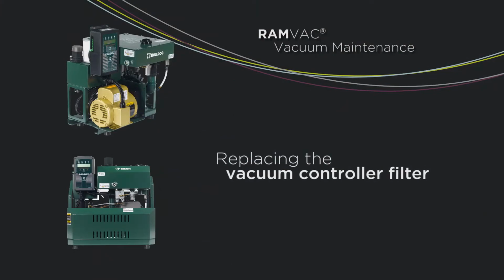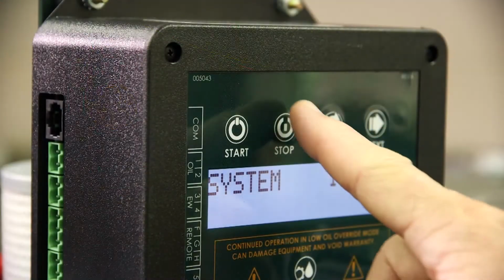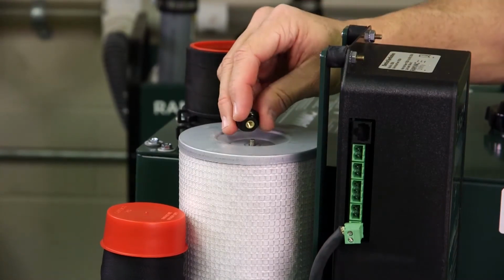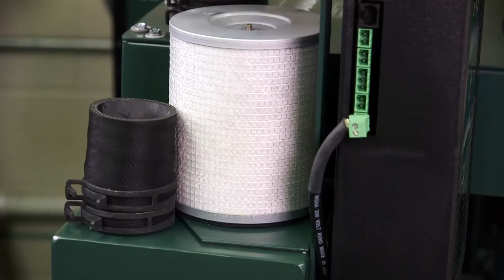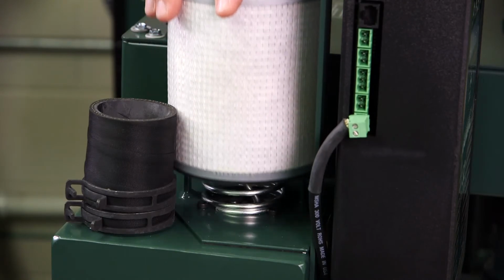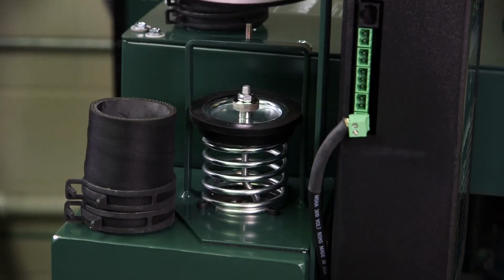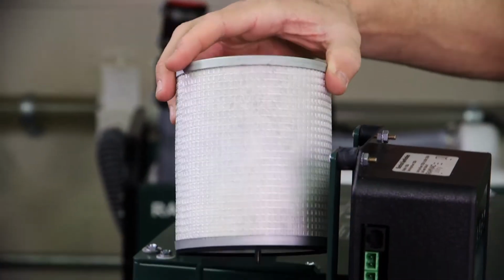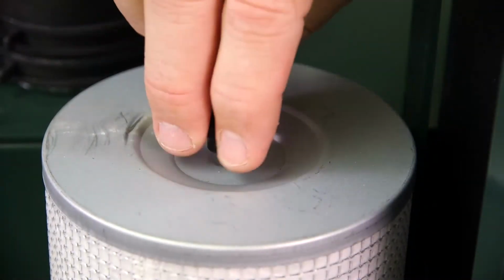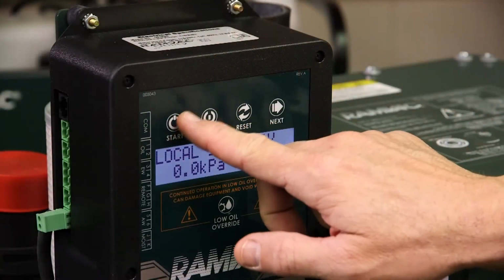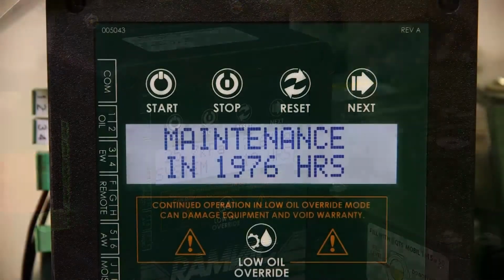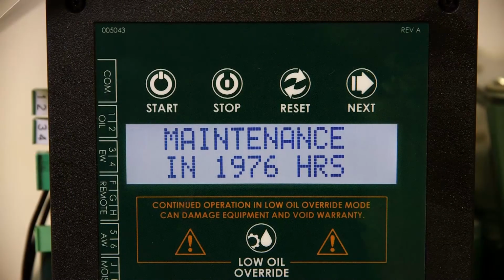Replacing the vacuum controller filter. First, turn the vacuum off. Then, remove the retaining nut off the top of the filter. Third, remove the vacuum controller filter by lifting the filter over the teepee. Fourth, discard the filter and replace with new. Last, return the vacuum pump to service. Reset the S2 control maintenance clock by pressing and holding the reset button for up to 10 seconds while the oil change screen is displayed.